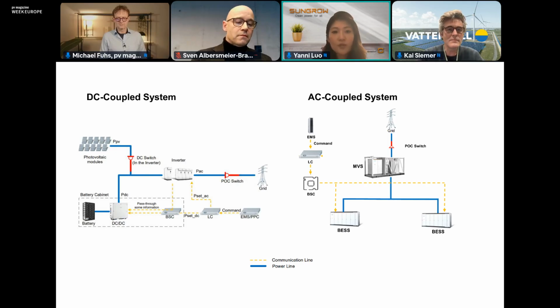Comparing DC coupled to AC coupled solutions, from a CapEx perspective you can save cost on cables and on the MV station, since you can share the MV station. But in practice there are always pros and cons with DC coupled solutions. The efficiency is much better than AC, because the 1+X central inverter has higher efficiency than the bi-directional power converter system we use for AC. But if you factor in that you cannot charge the battery from the grid, that's something we need to pay more attention to.